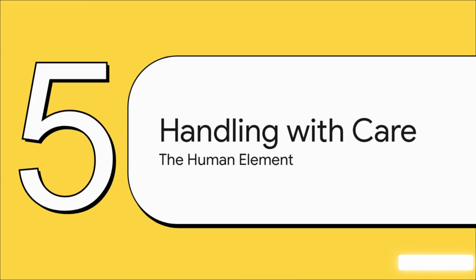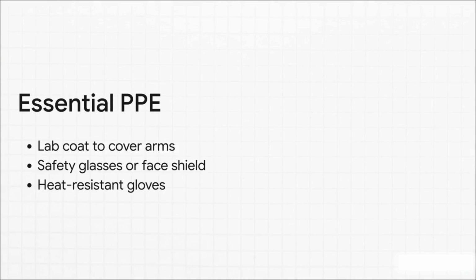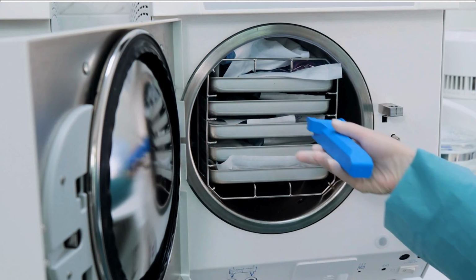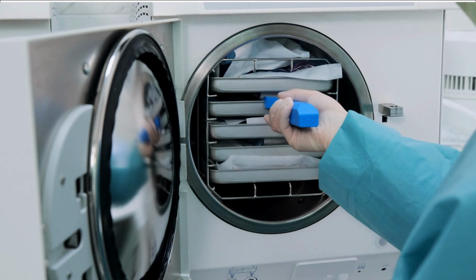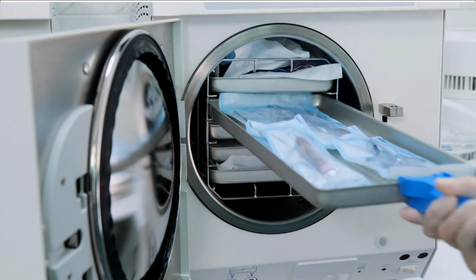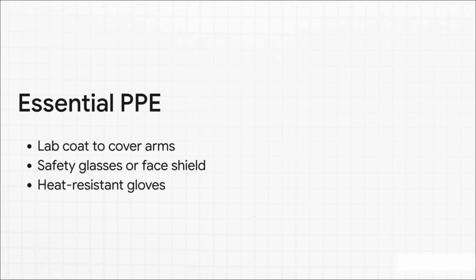Now, it goes without saying, any machine that uses extreme heat and intense pressure is by its very nature dangerous. So the final, and maybe the most important, piece of this whole puzzle is the human element operating the autoclave safely. This part is completely non-negotiable — you have to have the right personal protective equipment: a lab coat, safety glasses or a face shield, and most importantly, thick, heat-resistant gloves. You cannot underestimate the danger here. The items inside and the steam itself can cause horrific burns in the blink of an eye.